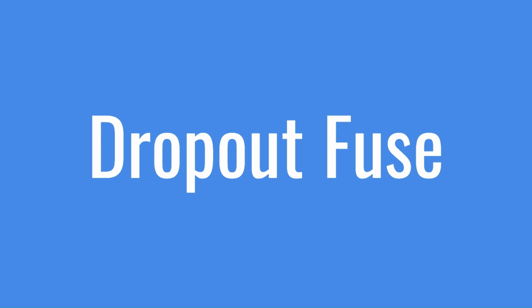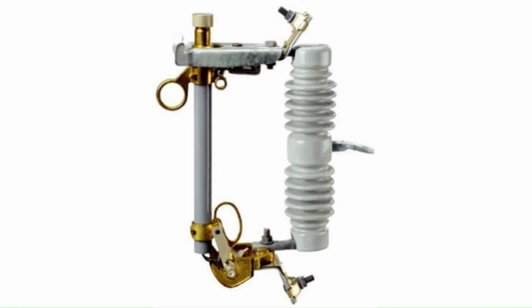The dropout fuse consists of a porcelain insulator, a fiberglass insulating fuse tube, and metal conductive parts. It acts as a protective device that breaks the circuit during a high voltage surge or fault, which prevents damage to the equipment. The dropout action means the fuse carrier hinges down, allowing for easy identification of the fault from the ground. Such type of fuse is used for the protection of outdoor transformers.